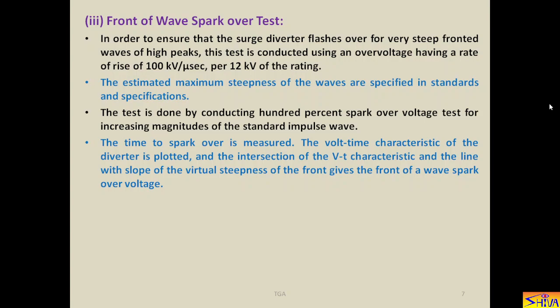Now see why this test is performed. For standardization, we are assuming that rise time of the impulse wave or impulse voltage is 1.2 microseconds. But in actual system, when lightning over voltage is occurring, it is not necessary that the rise time up to the peak is 1.2 microseconds. It can be less than this or it can be higher than this. If it is less than this, it means steepness of the wave is high. So our requirement is, even when voltage wave is very steep, the lightning arrestor should spark over. To ascertain that the lightning arrestor is operating with very steep fronted waves, this test is also performed.